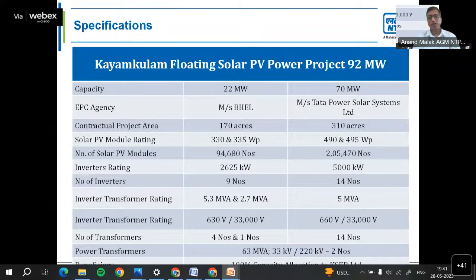For inverters, we have 2.625 megawatt units for the 22 megawatt plant; actually, they are rated for 2.5 megawatt. There are 9 of them, and for 70 megawatt we have 14 inverters of 5 megawatt. The inverter transformer ratings are 5.3 MVA and 2.7 MVA. In 70 megawatt, we have a 5 MVA inverter transformer, and the specialty of this 5 MVA rating is that it is based on ester oil. So if there is a leakage or anything, it will not have any adverse effect on the environment.